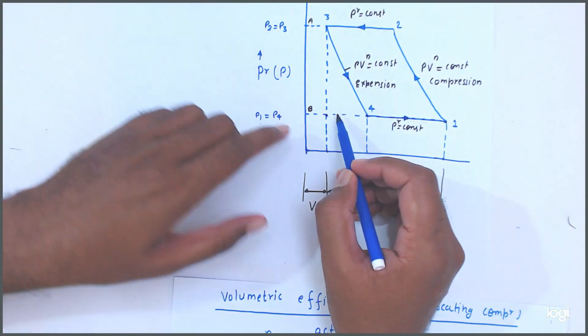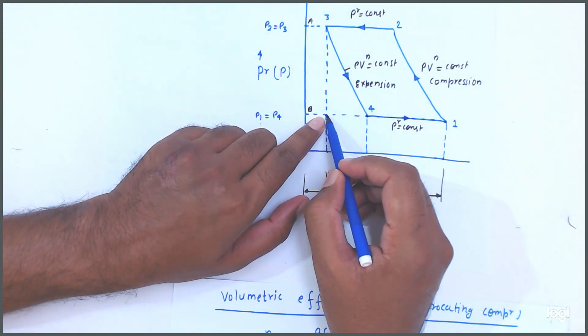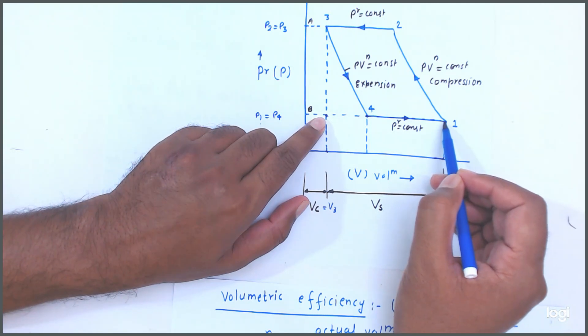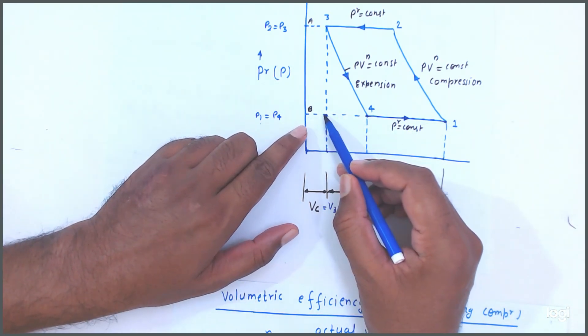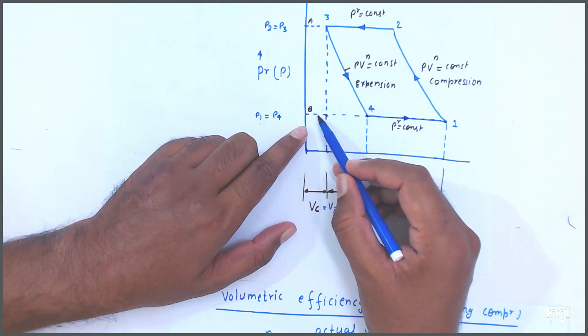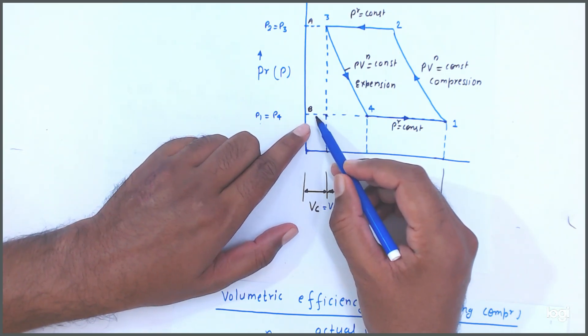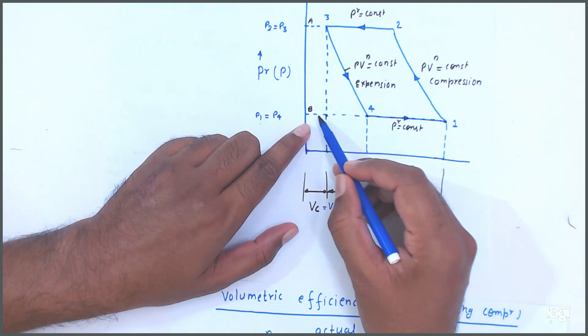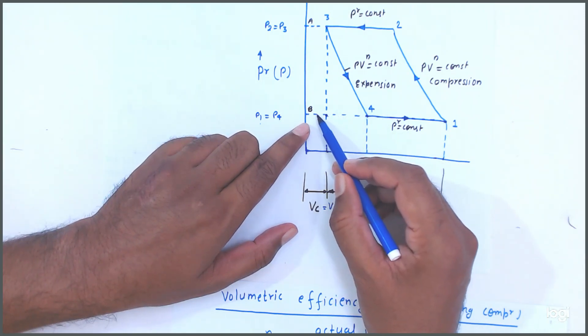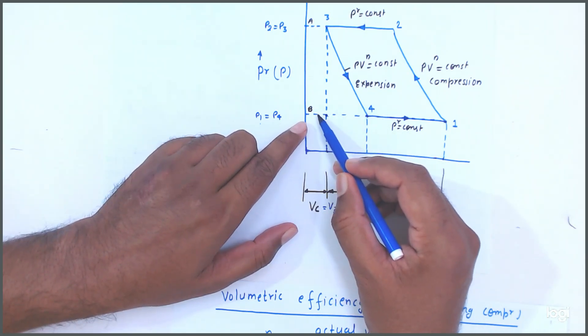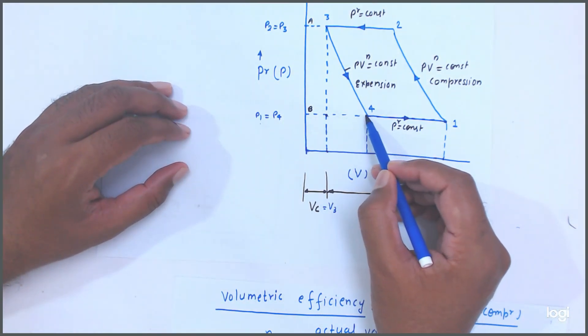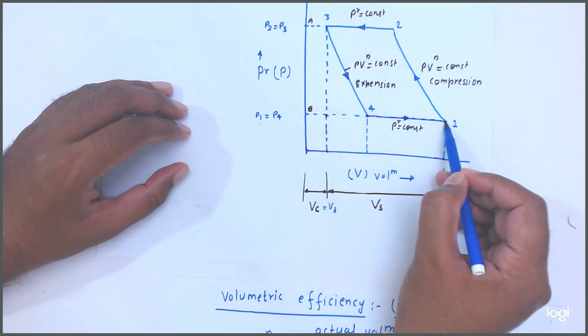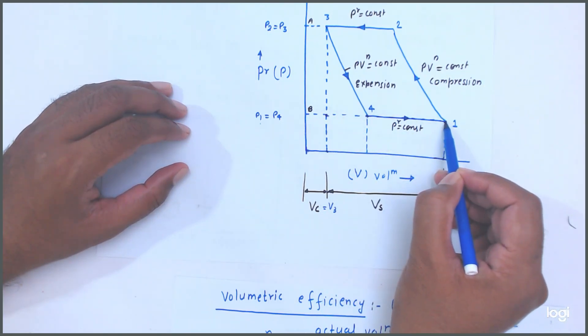In ideal condition, whatever volume should come in, it should be equal to the swept volume. But what happens friends, due to clearance volume, some gases — some air — get compressed inside. And when suction happens, the gases in the clearance volume expand, which reduces the actual suction volume. So this is the actual volume.